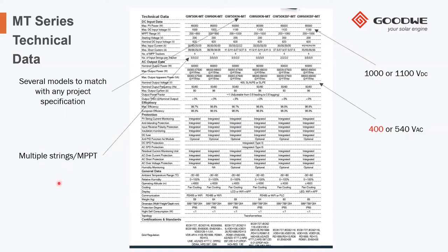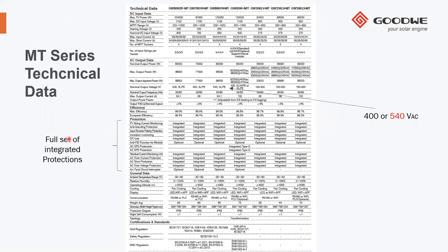You can have multiple string per each MPPT. You see here, they are reported in this row. And these are the next series, which you see the exit on the AC side is at 540 volts. But another extremely important point is the full set of integrated protection, which our MT series has. You can see here, we have the PV string current monitoring, anti-islanding protection, input reverse polarity protection, insulation monitoring, DC fuse, anti-PID, SPD, DC and AC side. So all of these protection are integrated in our system, which means you don't need to put this protection outside of this inverter. They are already integrated, so it's a big saving for your cost.